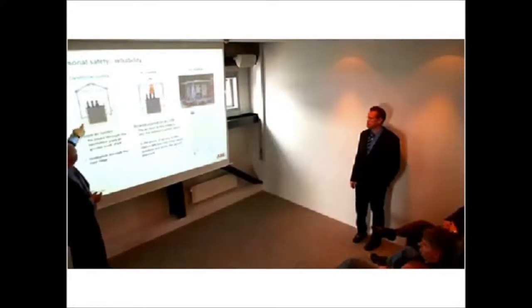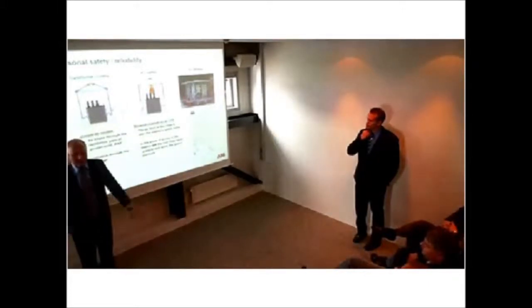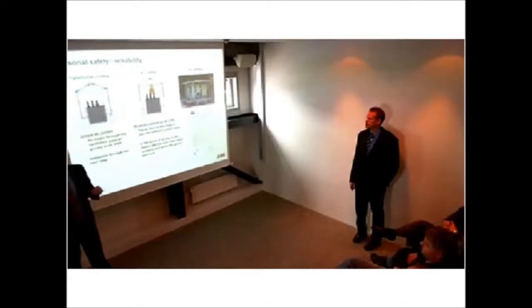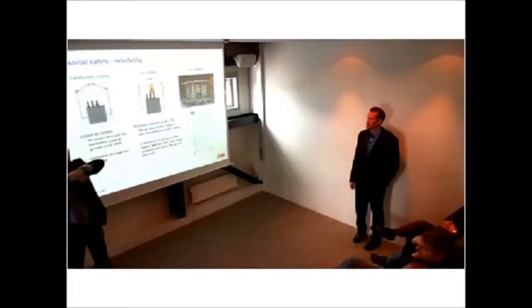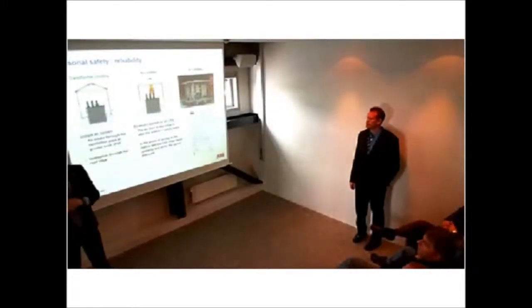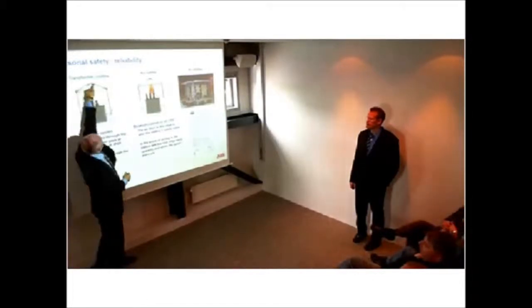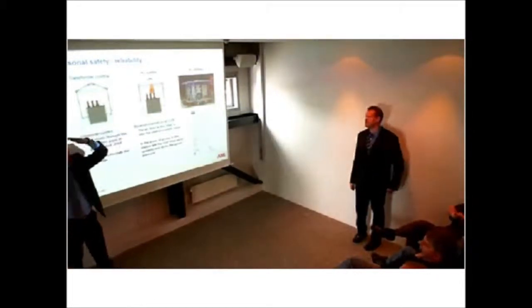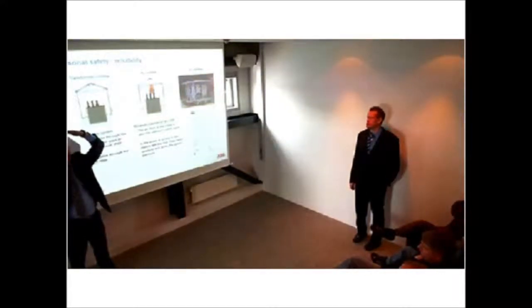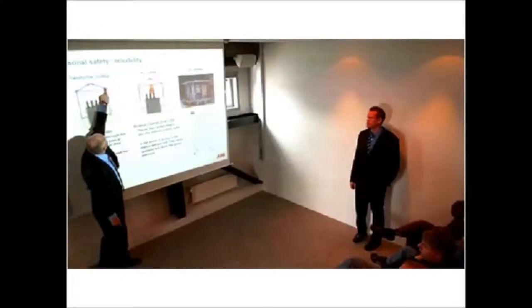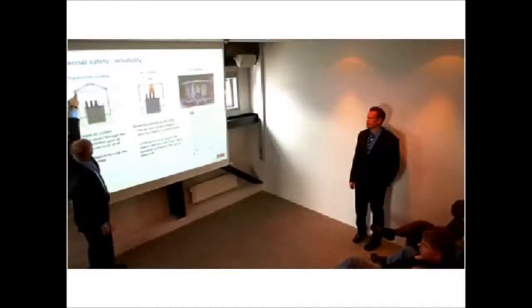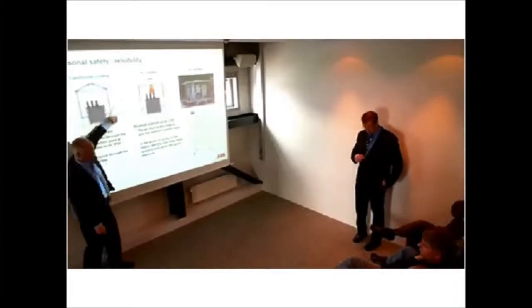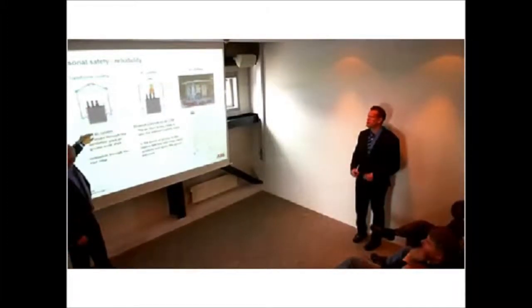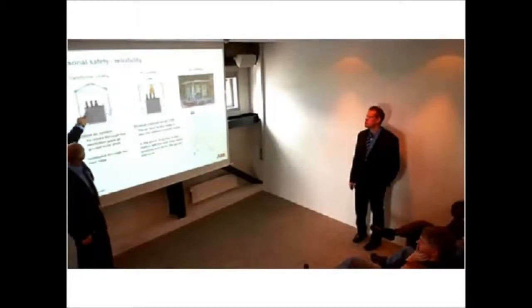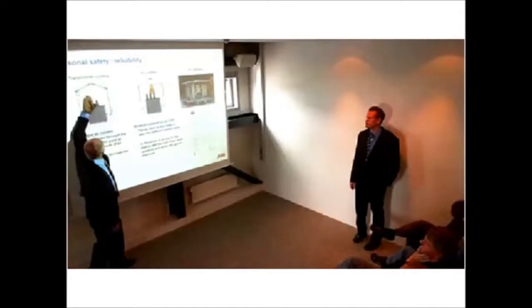In our design, we use the heat to circulate in the station. It's much easier to control the environment when you have a circulation of air. If you make a flat roof, you can have droplets on the switchgear and on the low voltage part. Our angle here is 20 degrees. By having 20 degrees, all the droplets will go to the side. They will go to this and or to that. And they will come down here, and they will not damage the switchgear. And also you have the cold air coming in, goes up, and it will escape here.